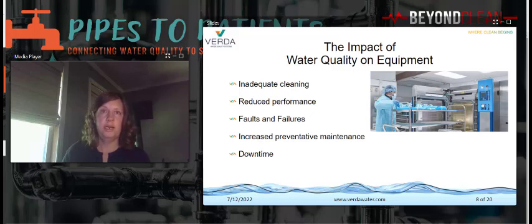So let's look at the water quality impact on performance of the equipment. Performance of reprocessing and water treatment equipment depends on the water quality. For instance, improper water quality can result in inactivation of detergents and cleaning enzymes, causing inadequate cleaning. This is true for manual cleaning of instruments, as well as automated washer disinfectors. Water hardness, pH levels, total organic carbon, and temperature are some of the water quality parameters that affect the performance of detergents. Scaling pipes, valves, and sensors from hard water can cause faults, failures, more frequent maintenance, and downtime.